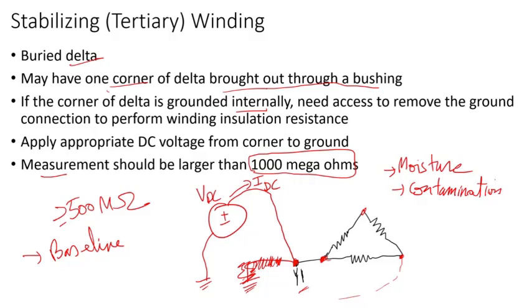This test is very important. Some people will say tertiary, but there is a difference between stabilizing and tertiary. Tertiary winding is loaded, connected to station service, and all three terminals of the delta are brought out. Stabilizing winding is really just for harmonic, triple harmonic suppression, and zero sequence currents.